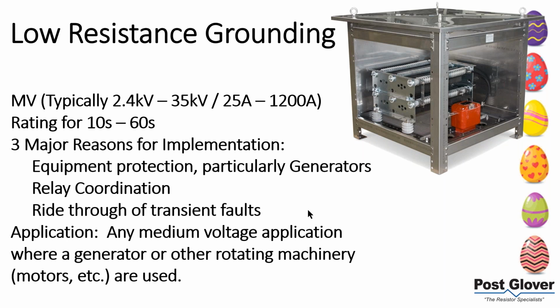Of course, you can ride through transient faults. This is typically a few cycle faults or something like that that may cause you to trip. Typically, this would allow you to be able to ride through that. So that's really, in terms of application, medium voltage application where a generator or other rotating machinery are used. That's true. There's others as well. We'll talk about that in a minute. But that's kind of the bread and butter of what we do.